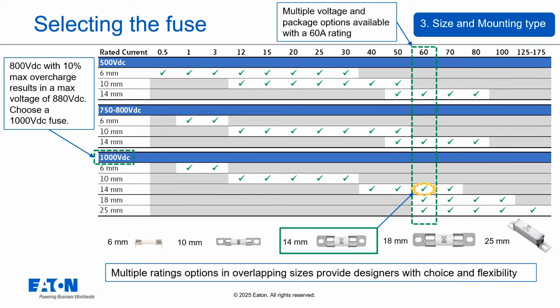Manufacturers offer multiple package options at different ratings. For a 60 amp 1000 volt fuse, there are various package options available. In this case, we choose the smallest offering from Eaton, which is 14 millimeters in diameter, and we have the ability to go up to a 70 amp rating in the same package in the future if we need to derate further.